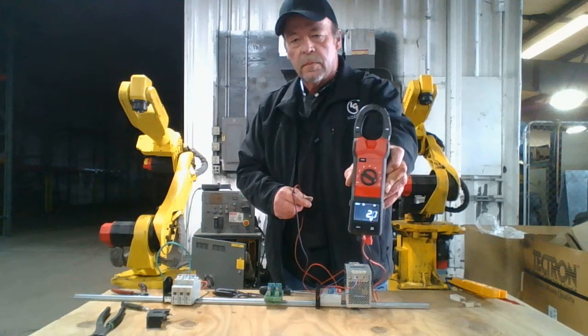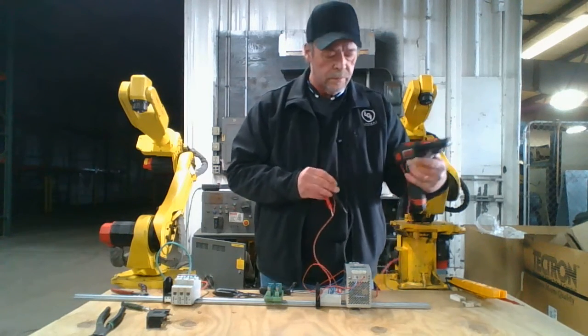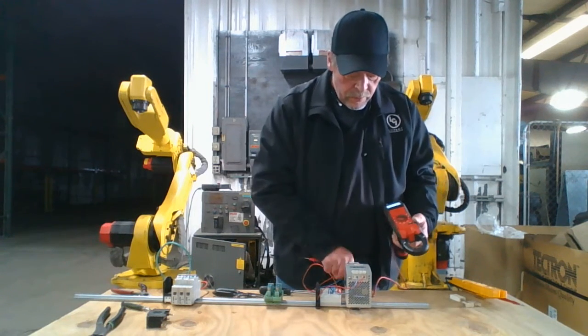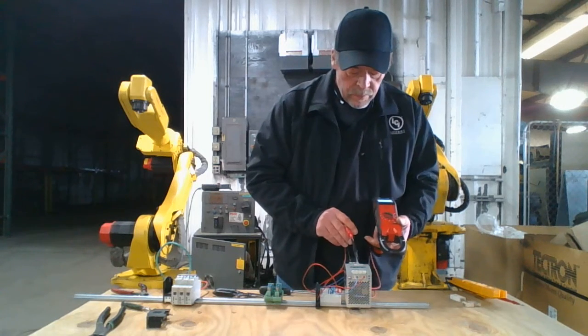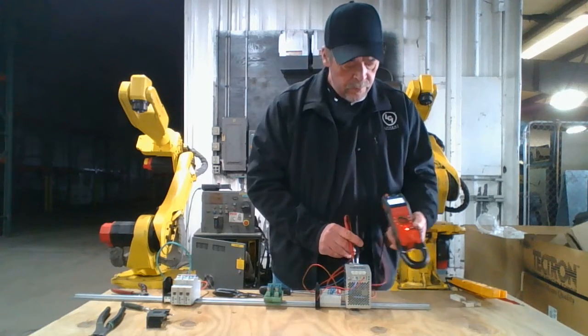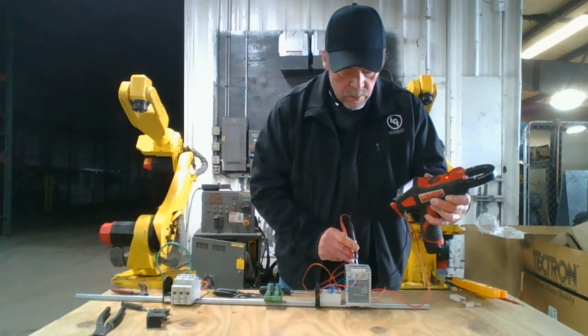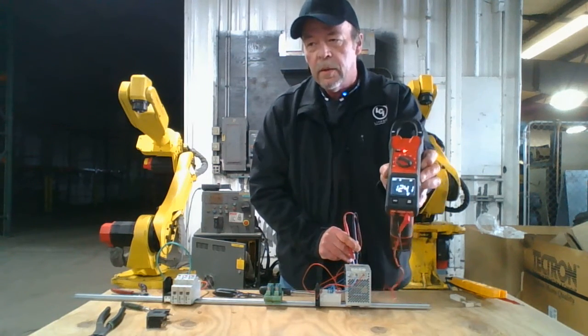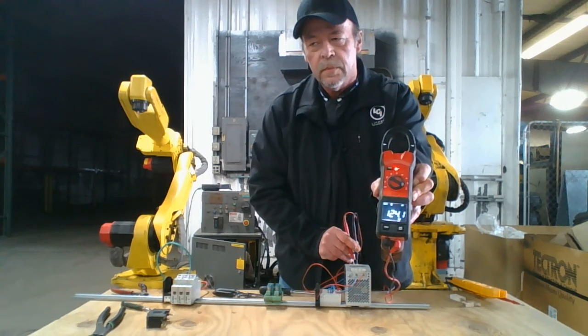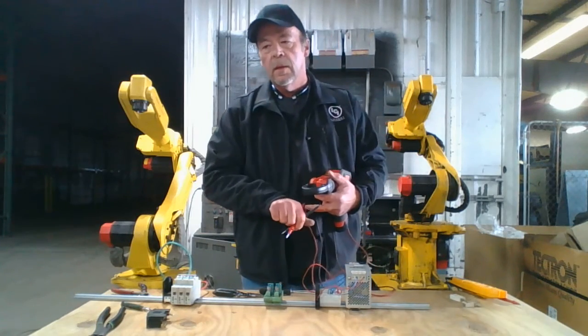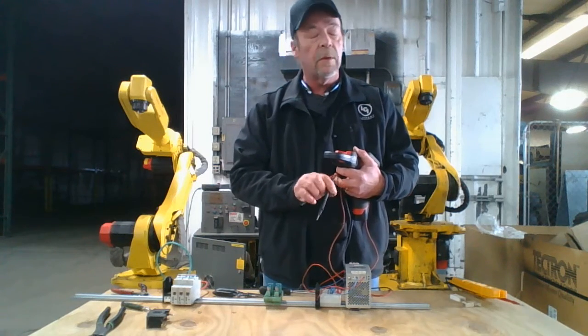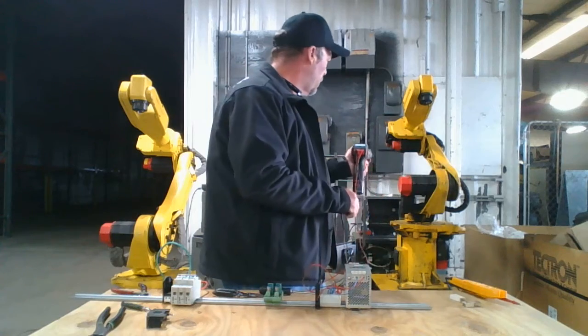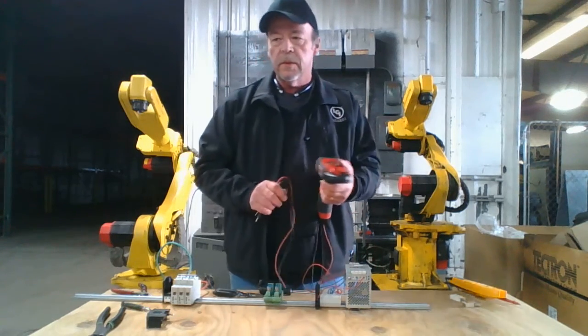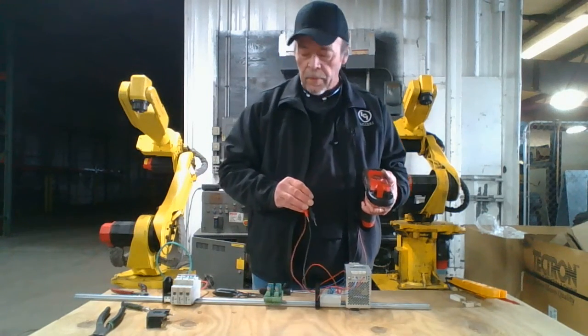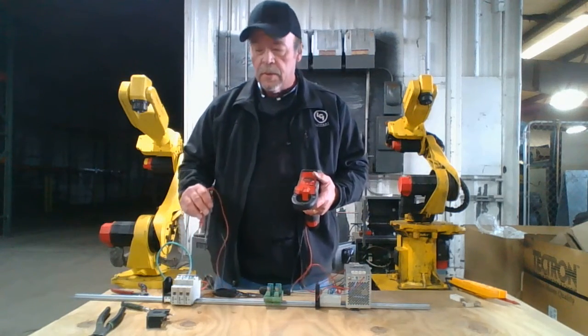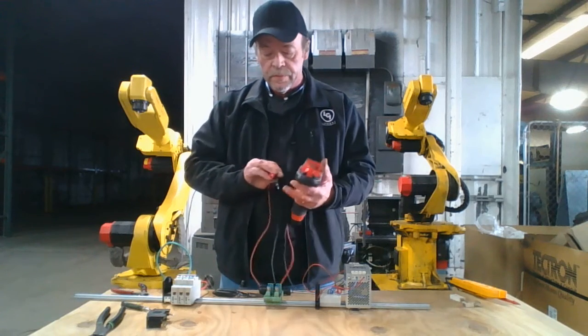Then you have your AC setting for volts. And my power here is running at 124 volts. The reason is because we run off a transformer. Our 115 volt power here, 120 volt, runs off of a transformer. I have a big transformer in the back behind this controller. I don't think you can see it, but that supplies my 120 volt. This is my 480. Now, we've talked before about whether it's Y or delta. This is delta.